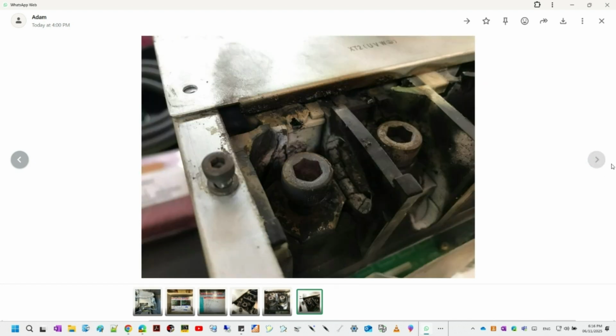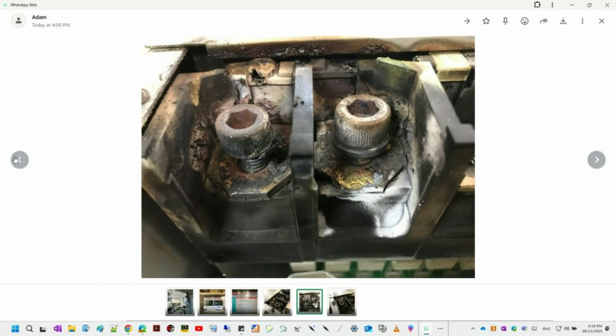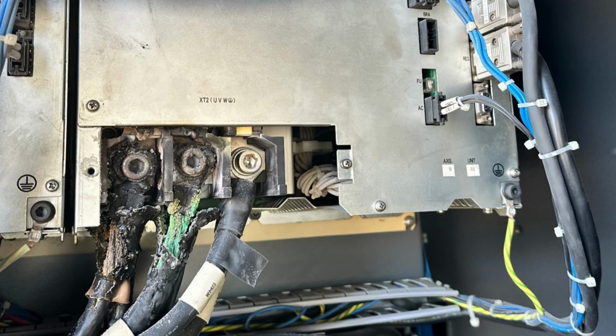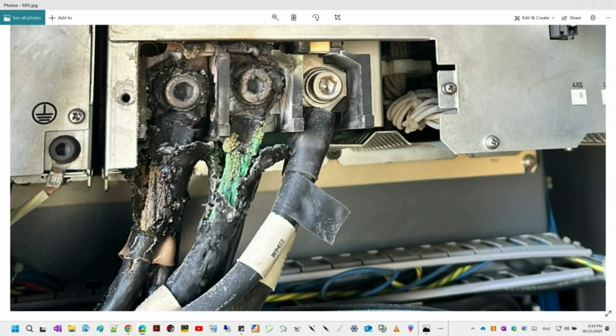Well, this incident was definitely a stark reminder of the importance of specific, targeted preventative maintenance. The chat log confirms they did actually have an annual PM schedule in place that included checking connections, and it was performed relatively recently, too, back in October 2024. But clearly, annual wasn't quite sufficient in this case, maybe due to the vibration or workload. Was there discussion about checking more often? Yes, the idea of more frequent checks, maybe even monthly, was brought up. However, the expert kind of pushed back on that, deeming it potentially excessive and maybe even counterproductive.